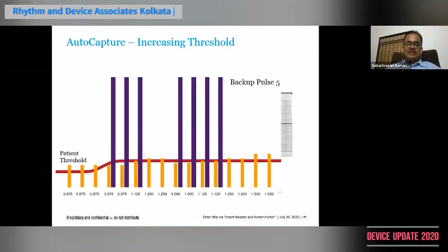It is always watching beat to beat. If there is any problem and the threshold rises, it immediately gives a backup pulse and runs a threshold test to find out the present threshold. Now the threshold has almost climbed to 1.25. This is determined, and subsequently the threshold is reconfirmed. After reconfirmation, the device starts pacing at 0.25 above the measured threshold, so it is 1.5. The most important thing is we never lost a single beat to loss of capture. Even if there was a loss of capture, there was always a backup pulse taking care of this patient. So this was the basic idea of this algorithm, so that patients should never have any problem of capture at any point of time.